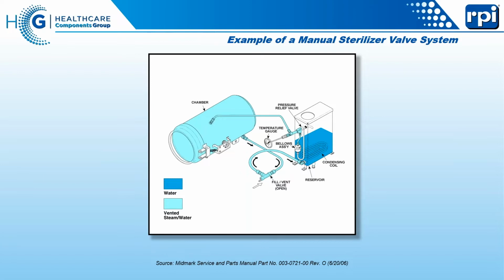When we're finished, after the amount of time we want the machine to sterilize, we reopen that valve again. All the steam flows out of the bottom of the chamber, back into the reservoir, where it's recondensed into water again. This reuses the water in the system to cool the steam - it's more economical on water and a little easier for the users.